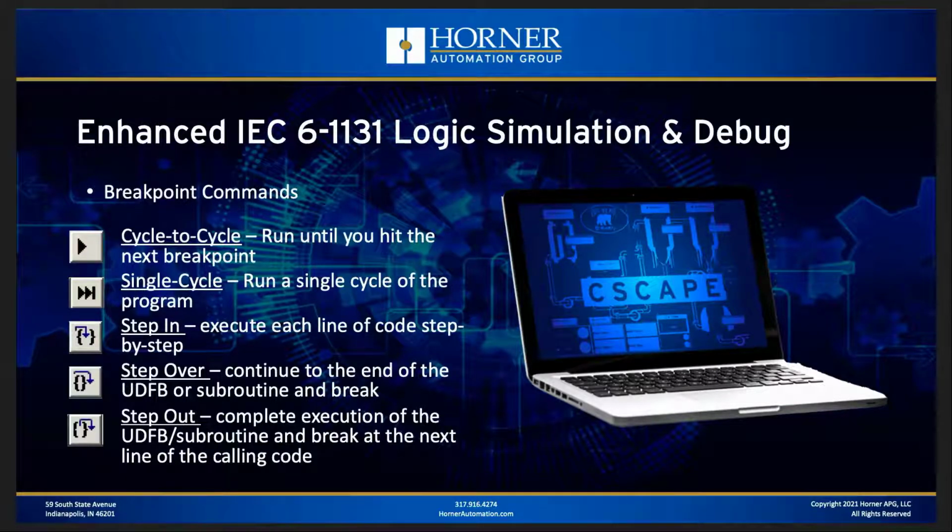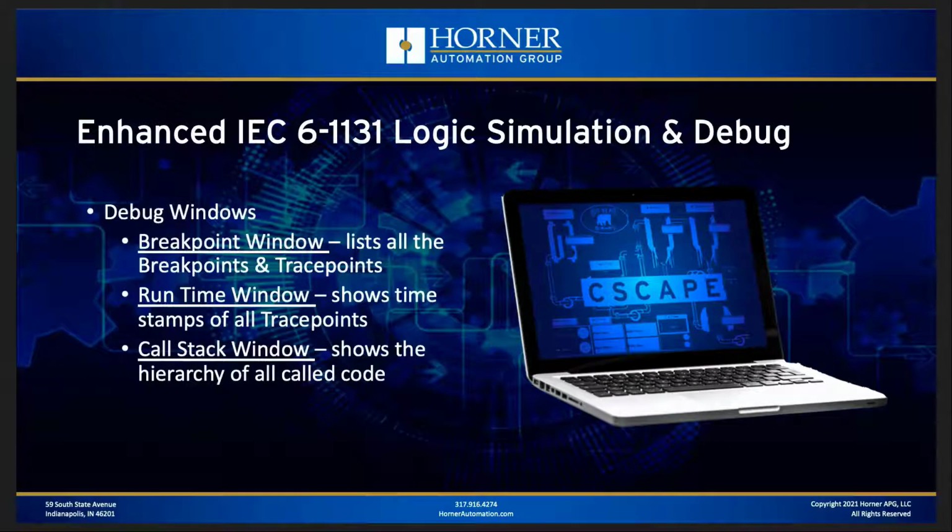And then there's a couple other buttons that are useful when you're dealing with subroutines. There's the step over button and the step out button, and I'll demonstrate those for you to show you how those can assist when you're troubleshooting your subroutines. One last thing: in addition to these trace points and breakpoints and the ability to tightly control how you work your way through your program, we also have some debug windows that are available where you can see at a glance the list of breakpoints and trace points that you've put in your program. You also have what's called a runtime window that shows you the timestamps for each of the trace points that you've hit during simulation mode.